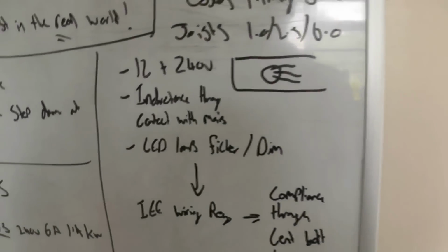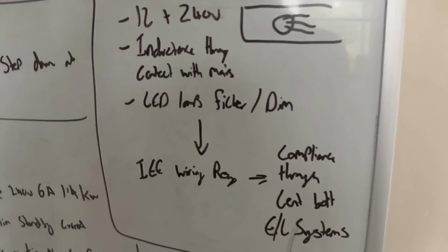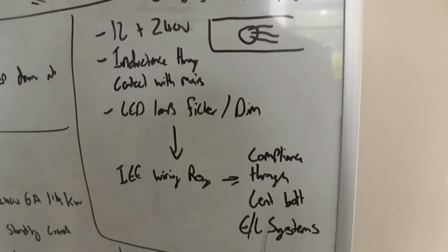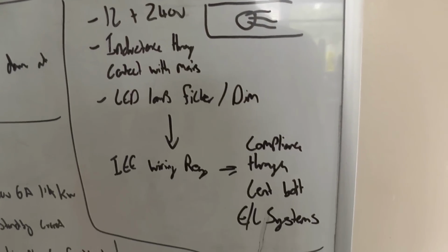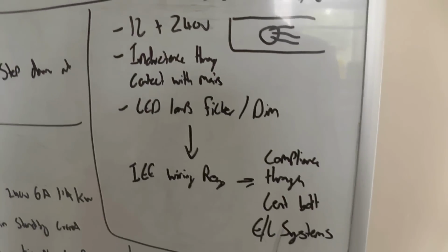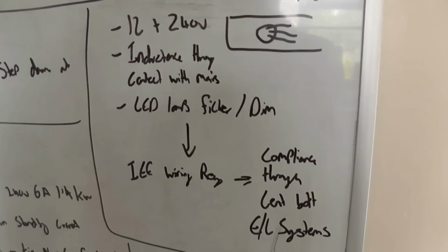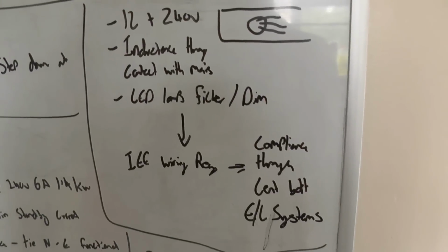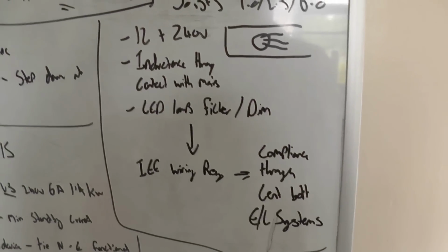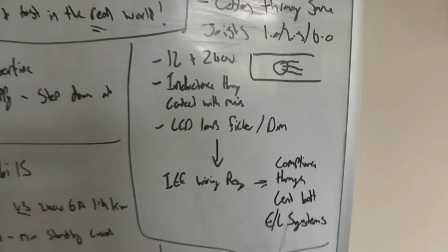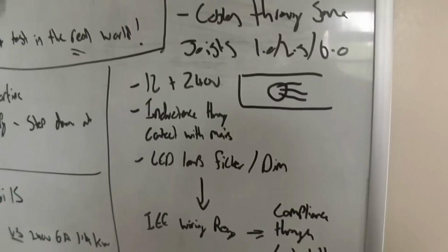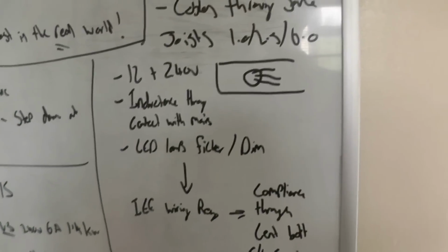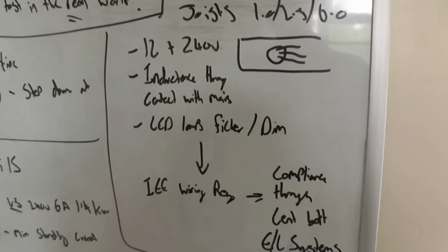which might highlight another problem I've had in the past, which is LED lamps flickering or being dim the whole time they're off. I have actually encountered this in this house. I swapped over a 50 watt halogen to a 3 watt LED, and every 5 to 10 seconds it would flicker and flash, and on the forums people say, oh, cheap lamp, let's wait for a good one. That's not the case. It is inductance from other cables charging the capacitor in the LED to a point where it tries to come on.